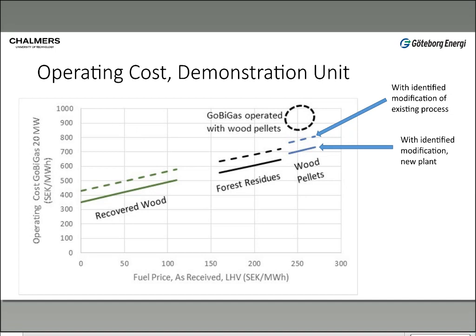All this happened with staffing costs, the personnel costs, representing some 20 euros per megawatt hour as an overhead, because the plant was run as a standalone unit. Had the second phase been built, it would have run from the same control room with the same staff, bringing this down considerably. If shared with more plants, it would be reduced even further, so this overhead wouldn't be part of the cost the way it is now. This graph shows the full personnel costs at this level.